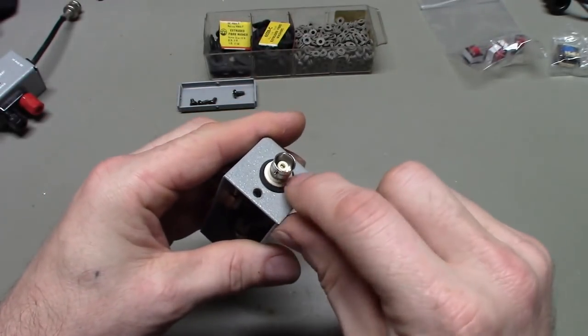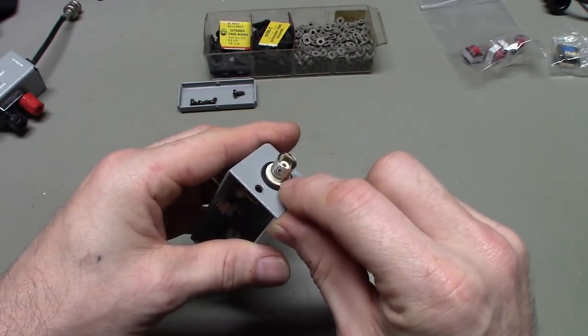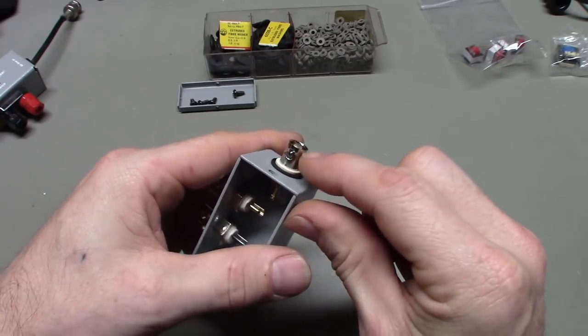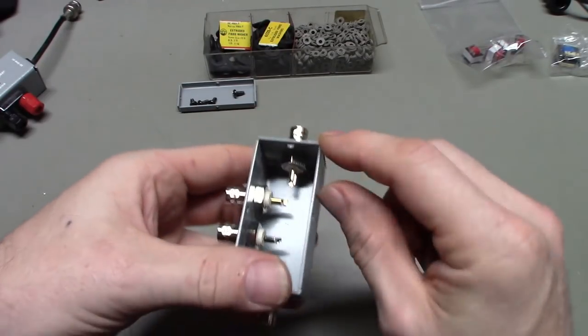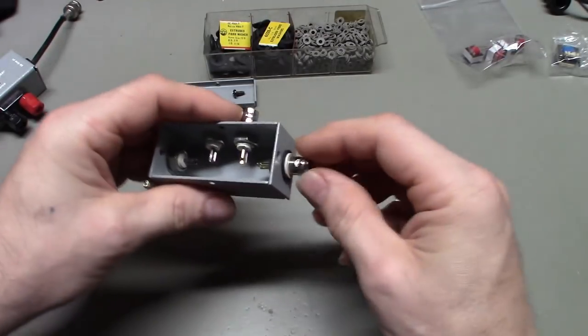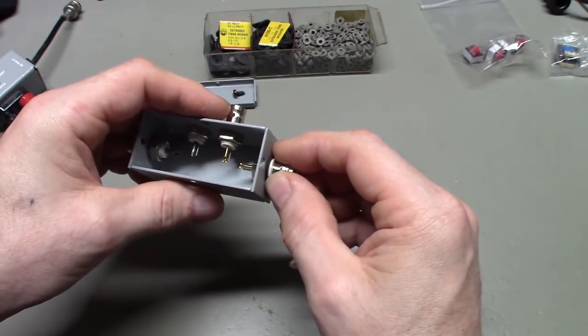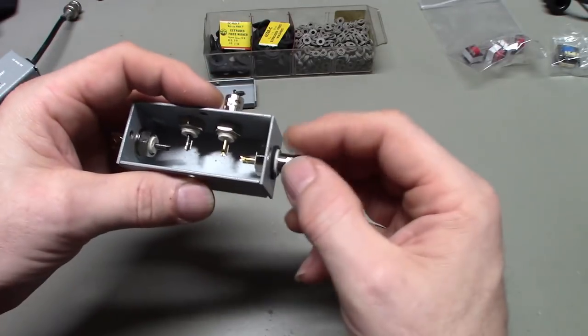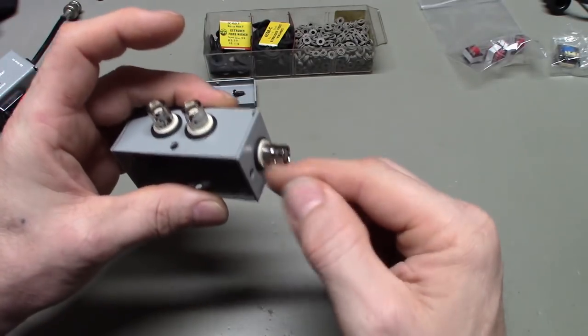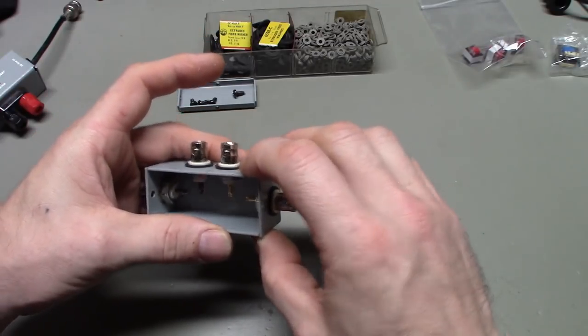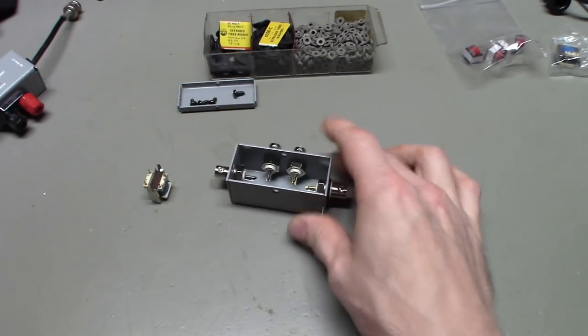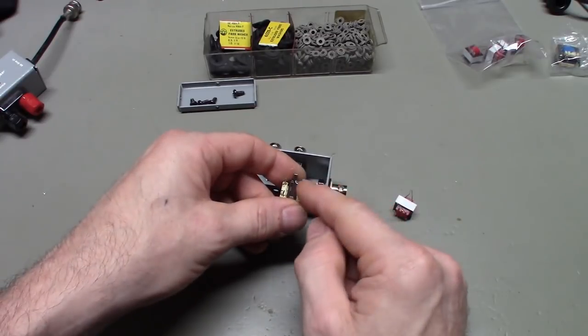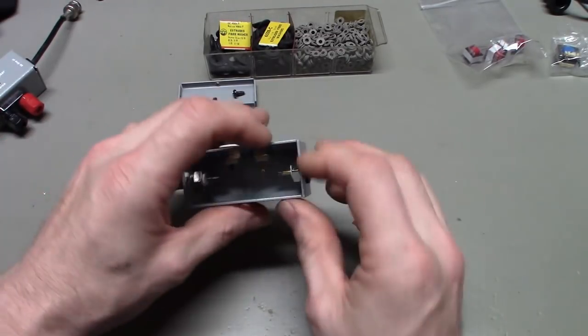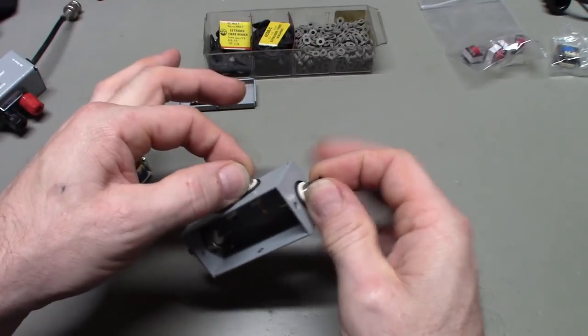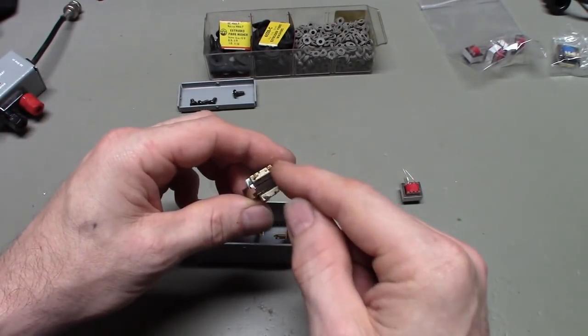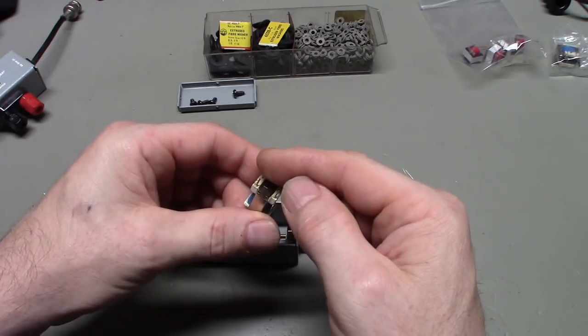I'm specifically using isolated BNC jacks, so the metal shield on this BNC jack has no connection to that nut. If you stuck a normal BNC jack into a metal box, when you tighten the nut up, the shield on the BNC is going to be touching the outside of the box. Even with an isolation transformer, if both BNC jacks are touching the metal box, you've effectively attached one side of the transformer to the other side.